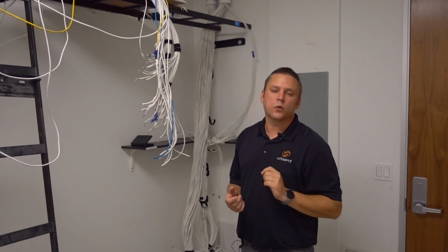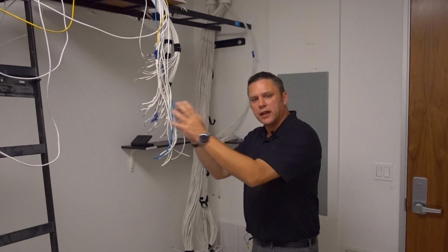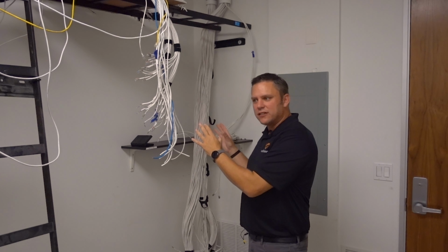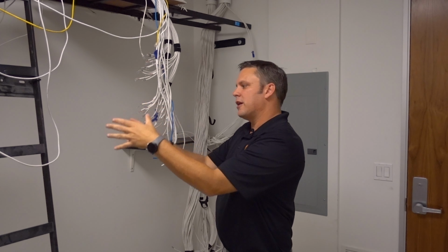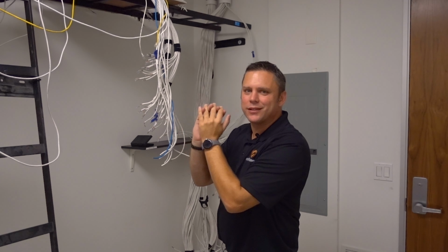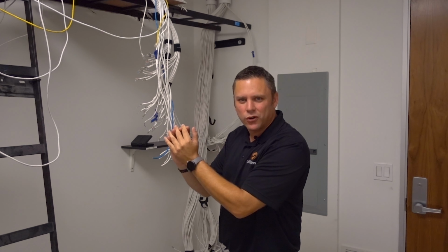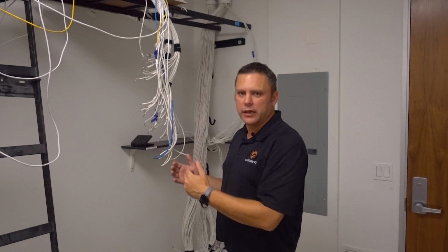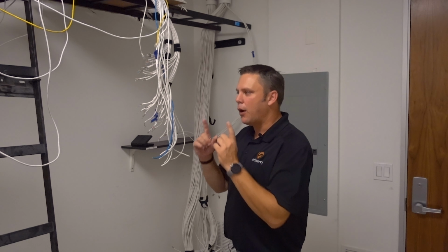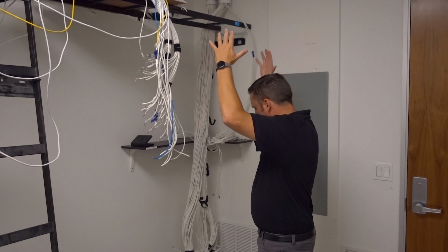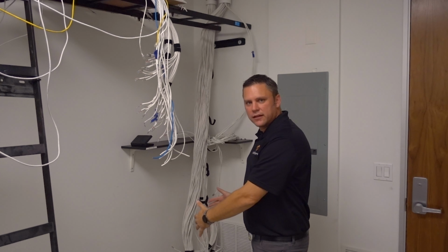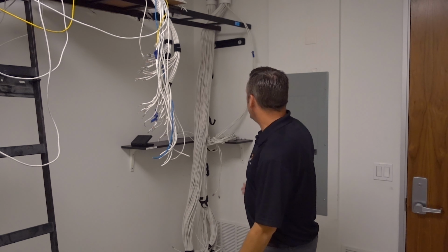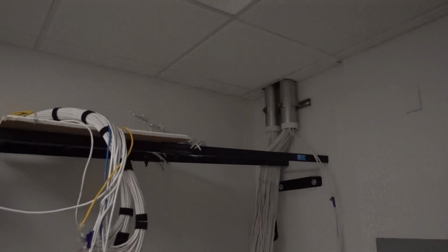There are situations where a server rack might have some stuff in it that belongs to the building, other stuff in it that belongs to the customer, or rather the customer has a system that's communicating with the building system, for instance, access control, and cutting that can cause a disruption if it isn't done properly or shut down properly before you do that. However, most of the time you can chop everything on the back of this server rack, get the server rack out of there, get it back set up, and what you end up with is all of your network cable.